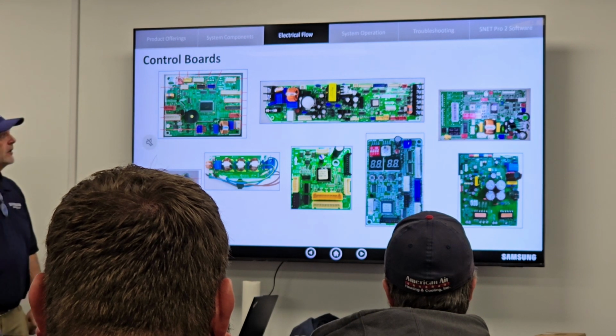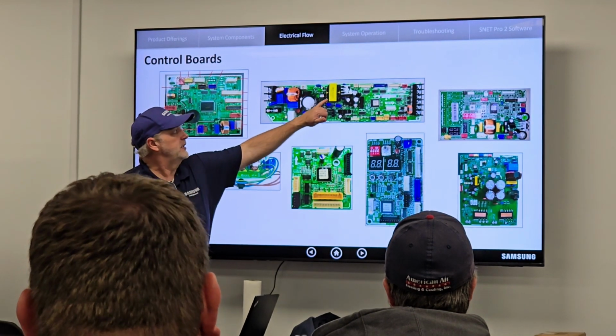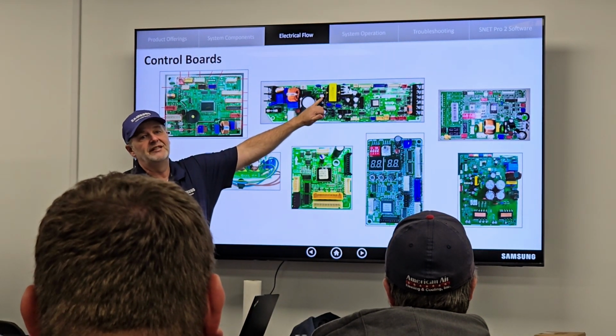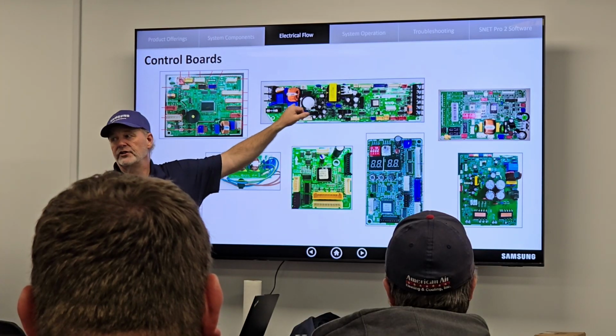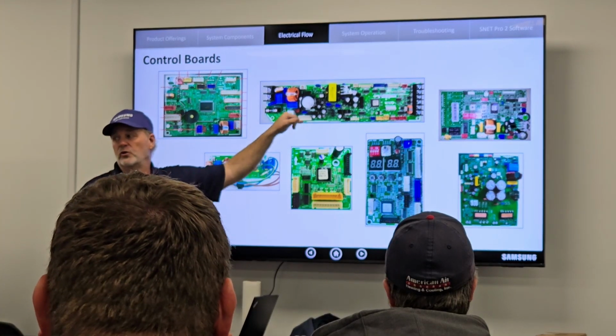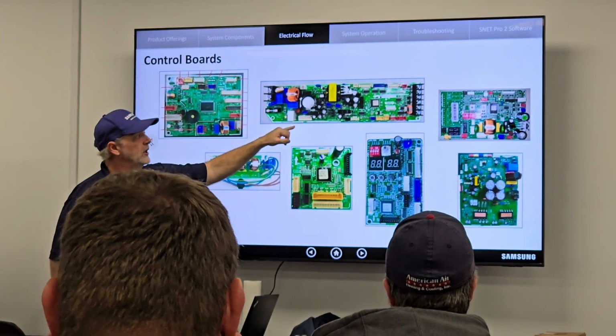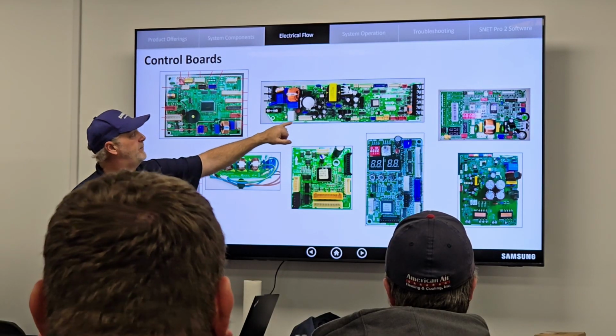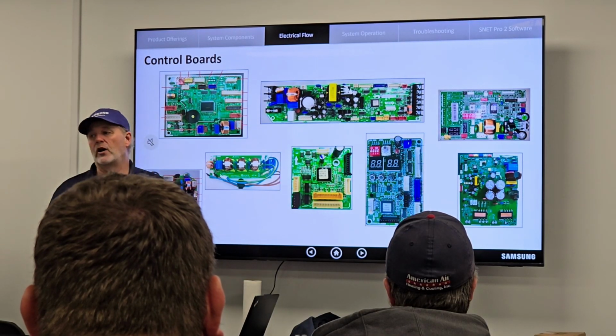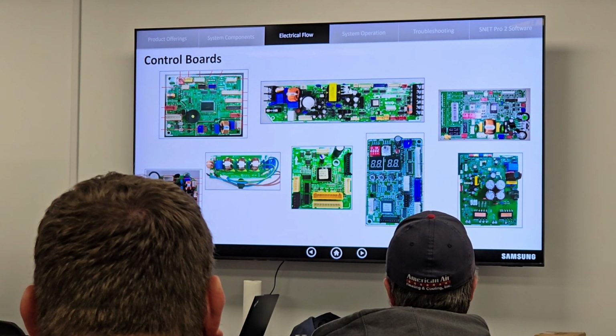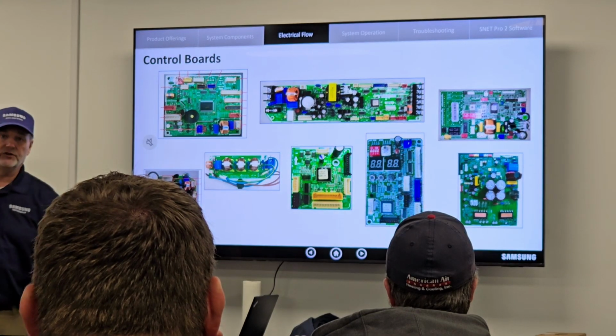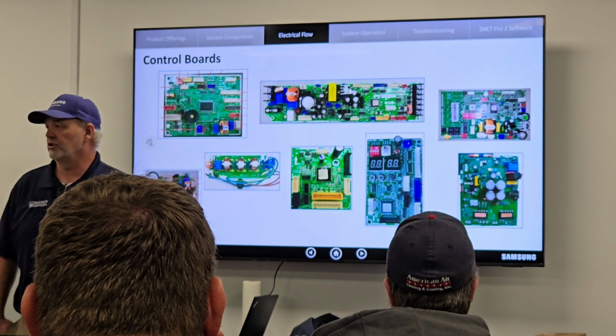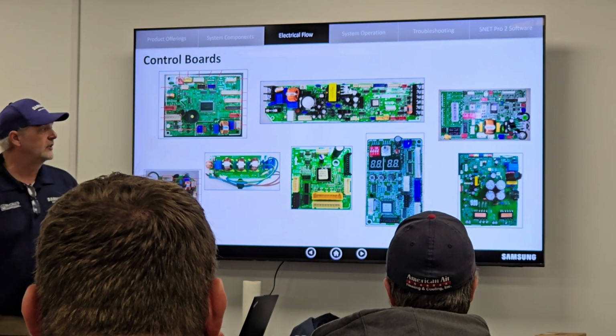Now here I have to point out, everybody see that transformer right there? What looks like a transformer? That's because we're rectifying voltage in this board as well. If I've got 230 volts coming into this board, it's now inverting. My evaporator fan motor is powered by what? DC, it's powered by DC voltage. It's called a DC link voltage. So we have to be mindful of that as well.